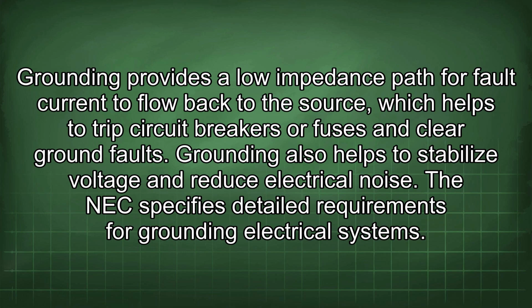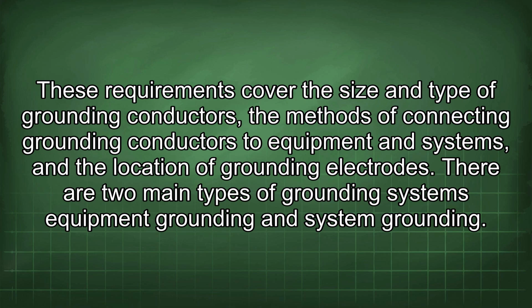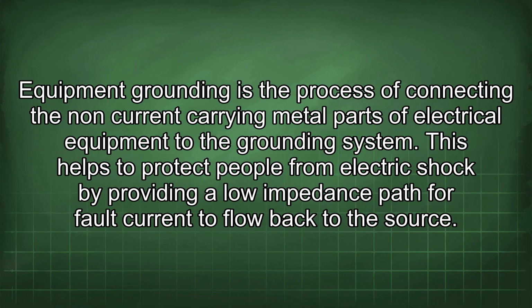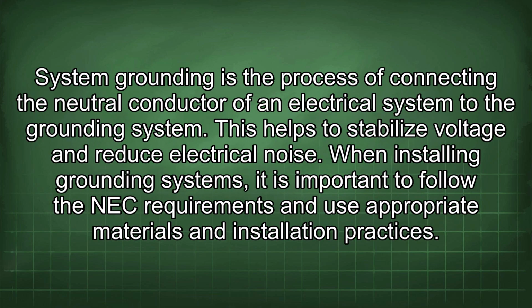The NEC specifies detailed requirements for grounding electrical systems. These requirements cover the size and type of grounding conductors, the methods of connecting grounding conductors to equipment and systems, and the location of grounding electrodes. There are two main types of grounding systems: equipment grounding and system grounding. Equipment grounding is the process of connecting the non-current carrying metal parts of electrical equipment to the grounding system. This helps to protect people from electric shock by providing a low impedance path for fault current to flow back to the source. System grounding is the process of connecting the neutral conductor of an electrical system to the grounding system. This helps to stabilize voltage and reduce electrical noise.